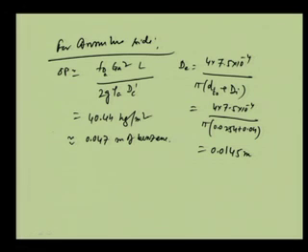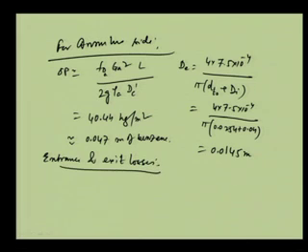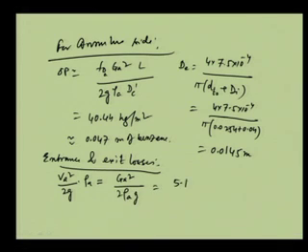But there is another, the entrance and exit losses. As we said, it is VA square by 2g into rho A, so nearly equal to GA square by twice rho A into g, and this is equal to 5.19 kg per meter square.